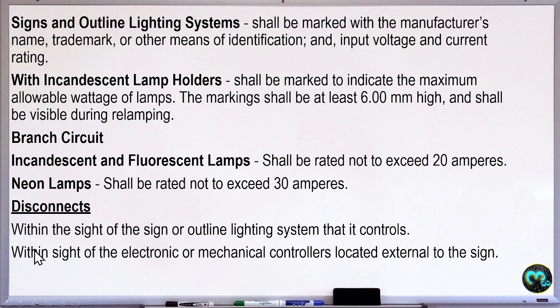Yung disconnects: the disconnect shall be within sight of the sign or outline system that it controls. So, kunyari ito ang billboard, dapat ang disconnect o breaker ay within the line of sight, mas malapit sa signage. Within sight of the electronic or mechanical controllers located external to the sign. If you have a motor controller na nakokontrol din ang sign, nagro-rotate siya, dapat nandun ang disconnect sa loob ng controller.